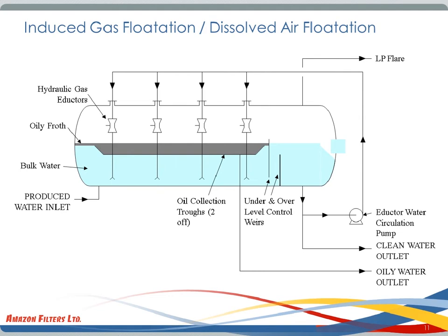in the induced gas or dissolved air flotation system, then we will have the gas being forced down into the produced water, which will then result in the layer of oil and solids rising to the top, where that can then be skimmed off. Dissolved air flotation can be used where there is no gas present within the produced water, and induced gas must be used where we have gas present, as we cannot have a mixture of flammable gas and air.